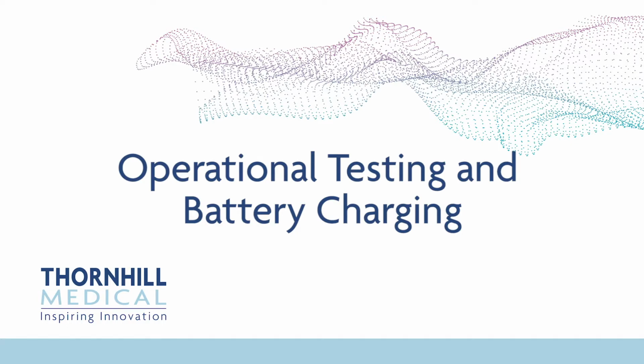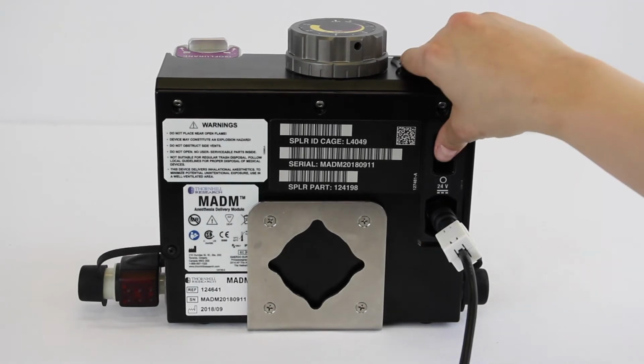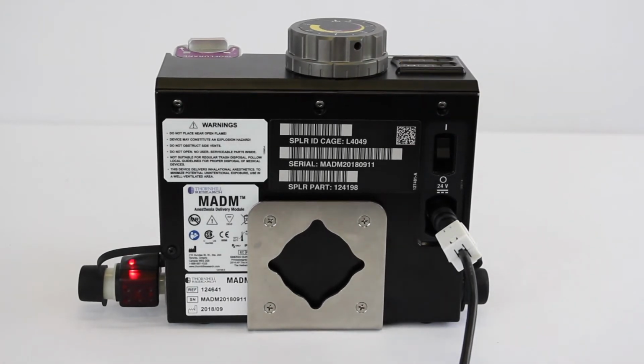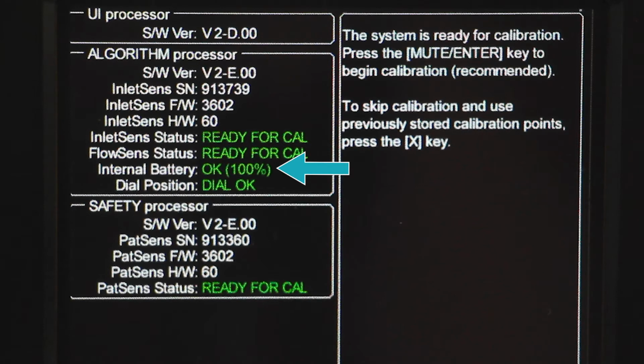Operational testing and battery charging. To check MADM's battery status, plug the MADM device into wall power and turn it on. To ensure that the battery status is okay, disconnect the power supply from the system and confirm that the battery is charged and the device stays powered.